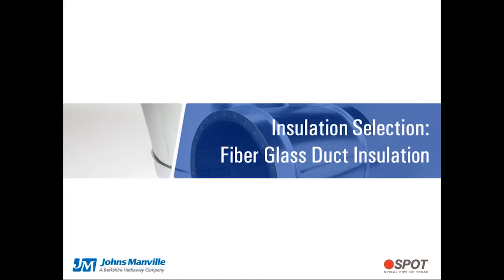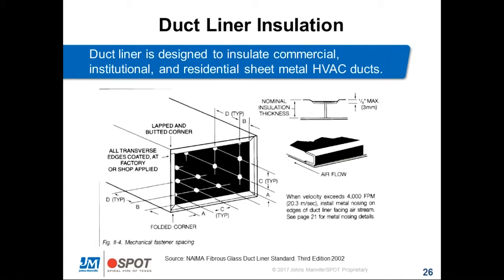Fiberglass duct insulation selection. Relative to duct liner insulation, duct liner is designed to insulate commercial, institutional, and residential sheet metal ducts. In the diagram here, you can see how a sheet metal duct is adhered and lined and pinned and mechanically fastened inside of a rectangular duct. You can find all the standards for the design and installation of sheet metal ductwork in the SMACNA HVAC Duct Construction Manual. They have a lot of really great information in there, and they'll talk about nosings, pin schedules, things like that.